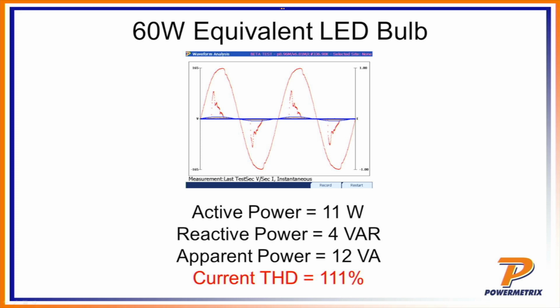The bulb itself will run cool, but the base, of course, actually has a converter in it. LEDs are DC lighting sources. So what that means is you're taking that 120 volts AC signal, you're converting that to a DC voltage, and that's being provided to the LED to be able to light that bulb. That AC to DC conversion is via what's called a switching power supply. Switching power supplies are probably one of the worst nonlinear loads that we have out on systems today. And so as such, it's generating, in this particular example, 111% of the energy as harmonics, and so that's a lot of heat.